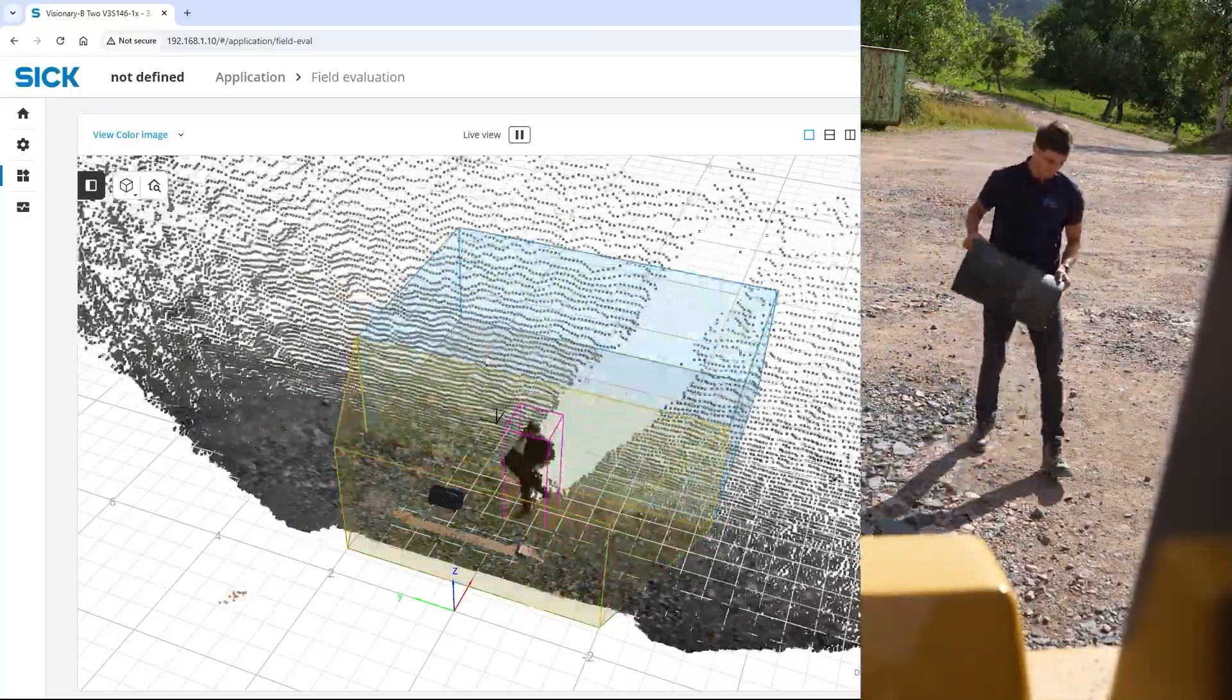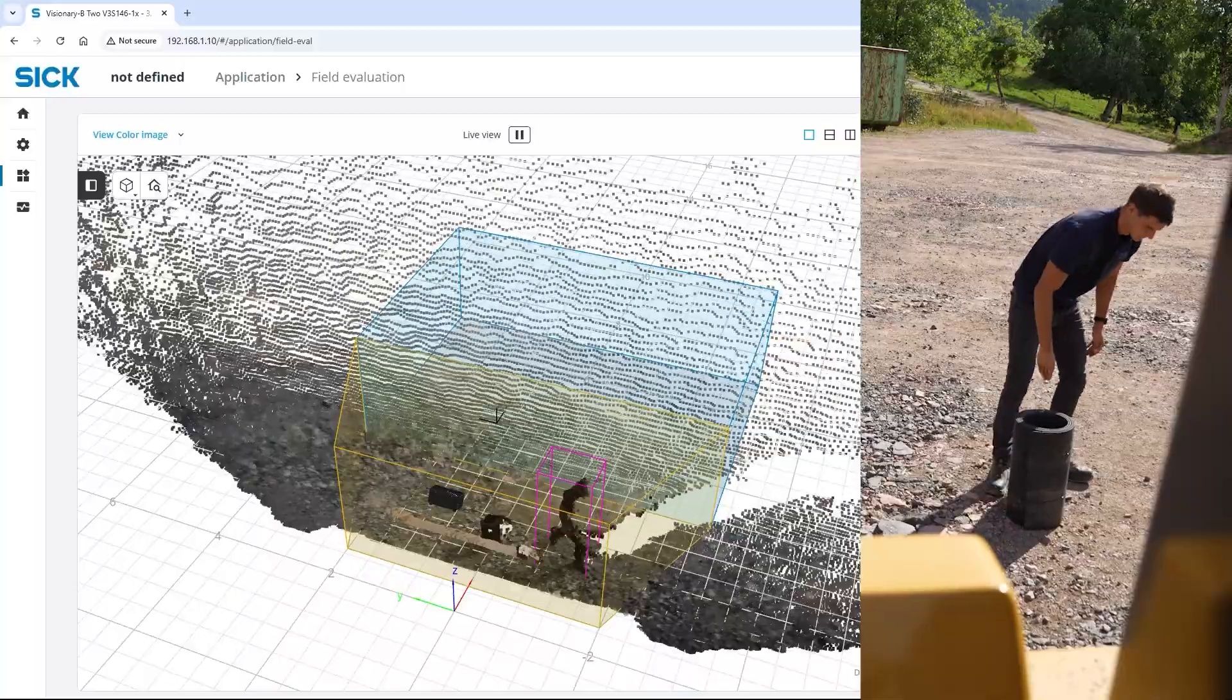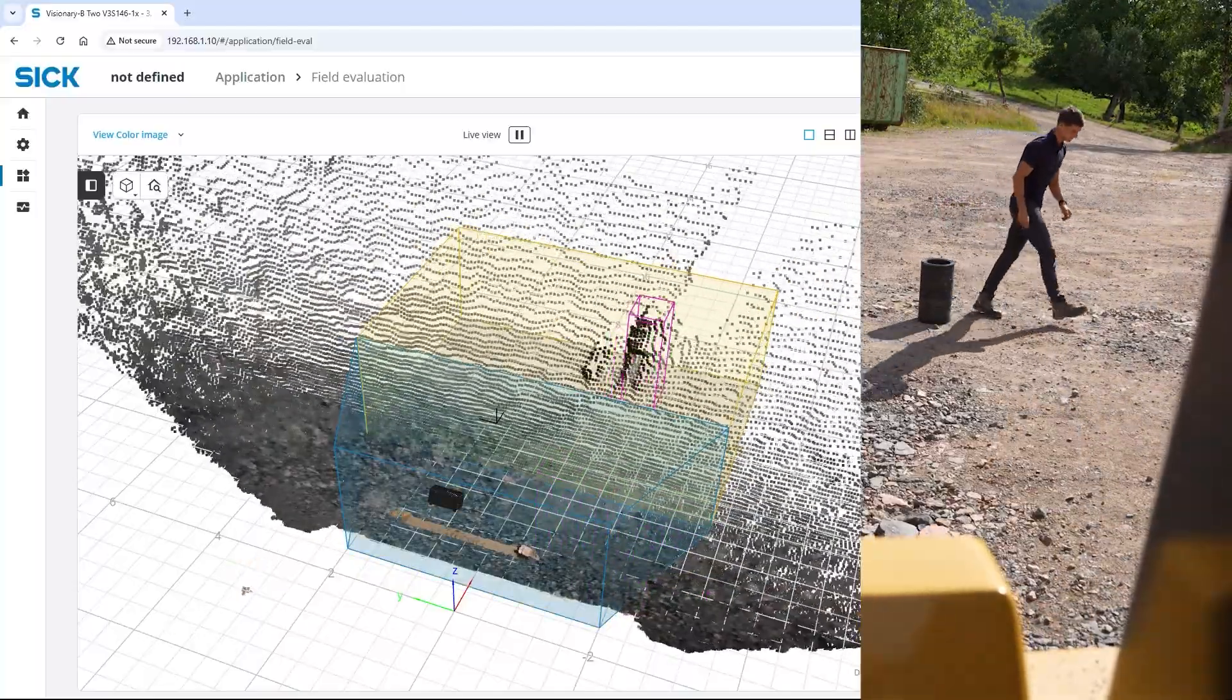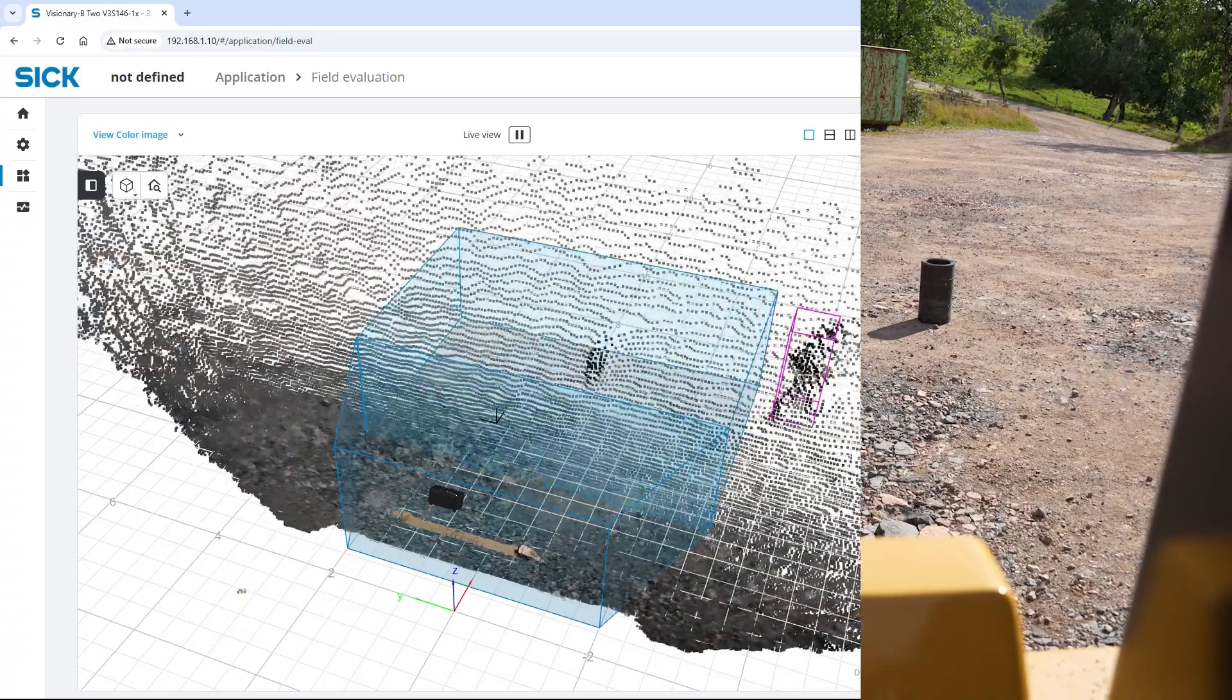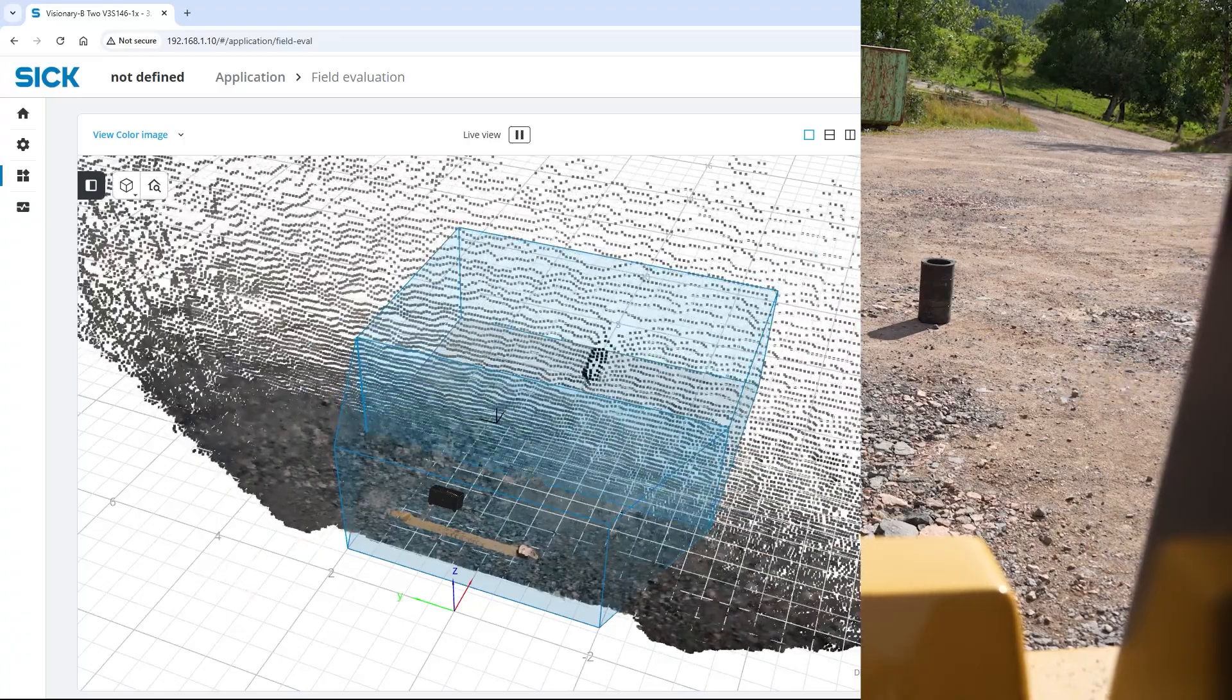Our test object is only detected in the stop field close to the machine. Placing it in the warning field does not result in a detection, which is correct as we only want to detect persons.